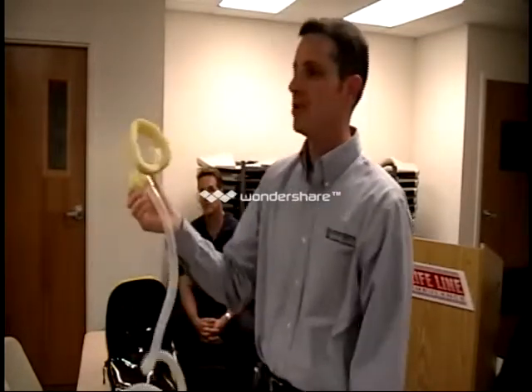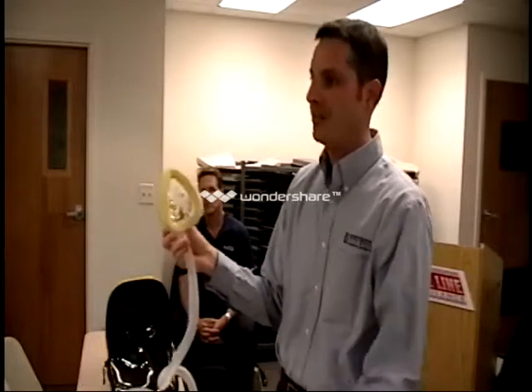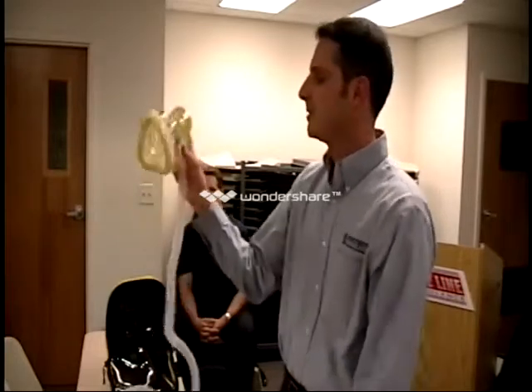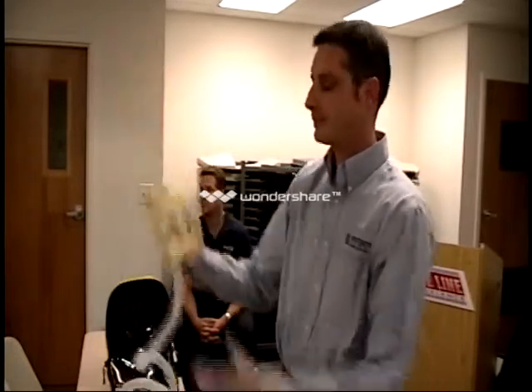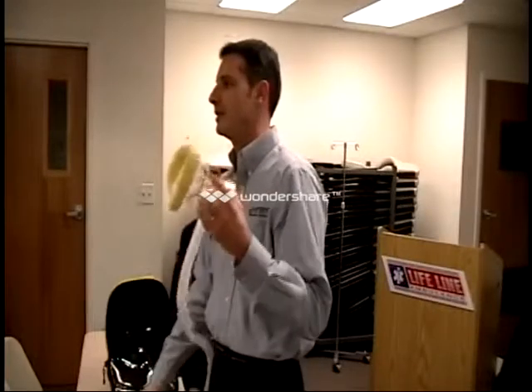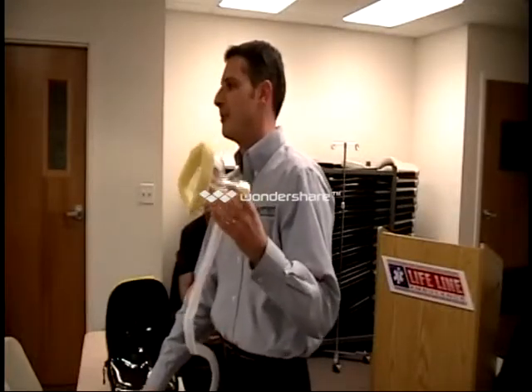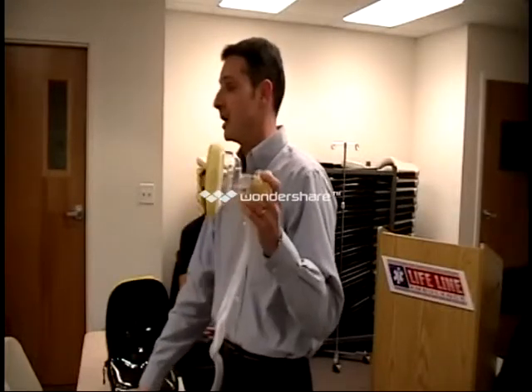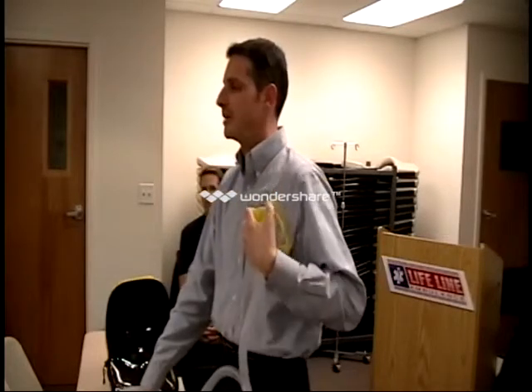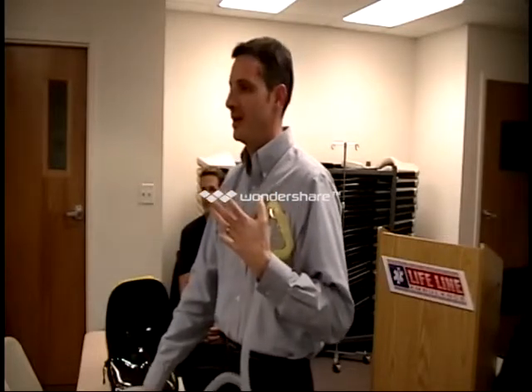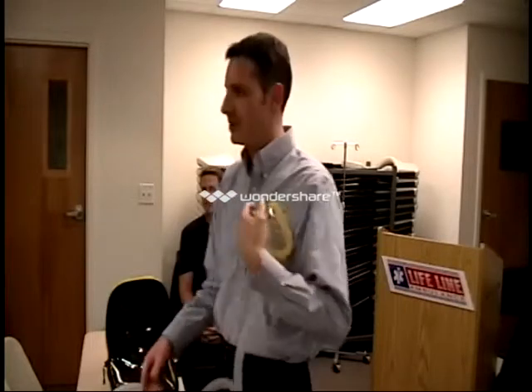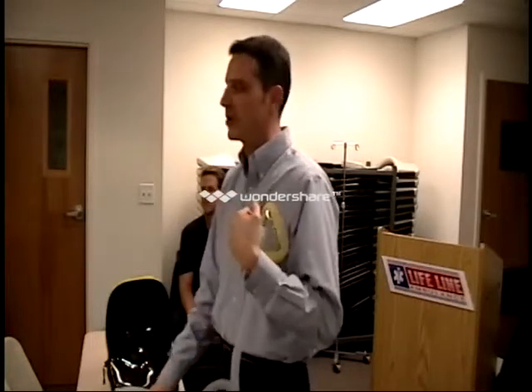Probably won't see that, but if you do drop the circuit and it's continually flowing, you get kind of baffled as to why you can't get a good seal. Just double check, make sure that thing's sitting flat. You never ever want to let this flow without being on a patient's face. This is 100 liters a minute. This will burn through your D cylinder in about 10 minutes, probably less than that. 100 liters a minute times 2,000 PSI is probably about 4 or 5 minutes. It's going to go through fast.